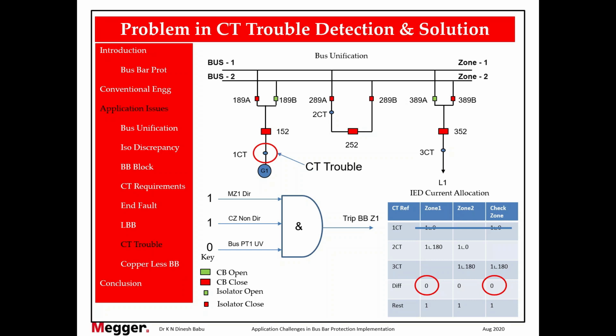Check zone has also picked up because the current is not available. But the bus PT will not pick up. So CT trouble has not blocked the zone, and the relay also has not tripped. We have taken a very rare scenario. Otherwise, main zone also would not pick up. So only non-directional would pick up.